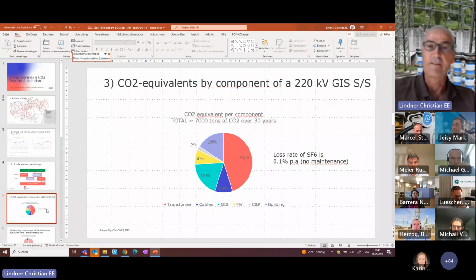No surprise: almost 50% of the CO2 equivalent for the substation comes from the transformers, from the bill of materials plus losses. The GIS—I'll jump into that a bit later—is about 20%, but this is an SF6 solution, not an SF6-free one. In total it's about 7,000 tons.